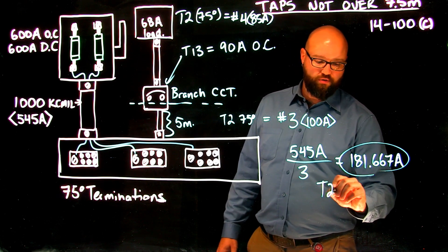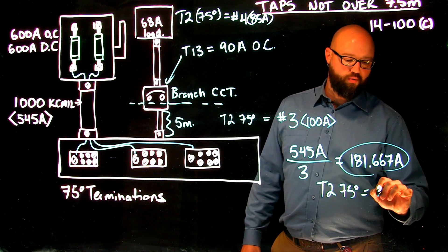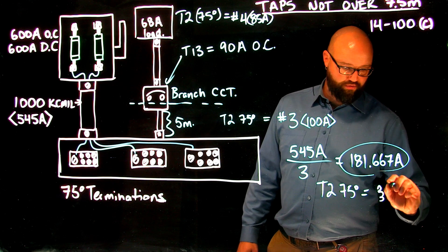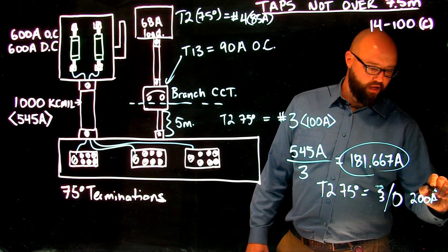So we go to table two, 75-degree column, and it turns out that we actually need to go with a 3-aught good for 200 amps.